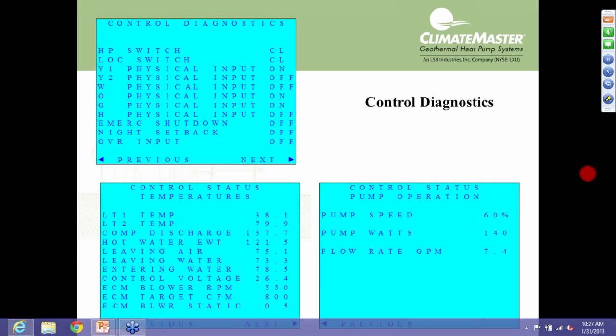The last item says ECM blower static. Currently, we are not calculating static pressure. We will be doing that in a future revision of our control. But right now, it's going to say NA. So don't be alarmed if you get one of these units and it says NA there. Right now, we're not calculating static pressure.